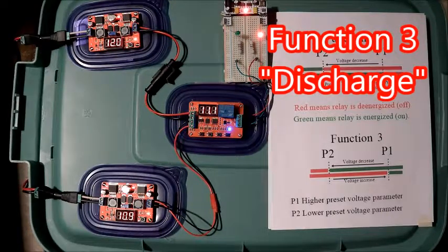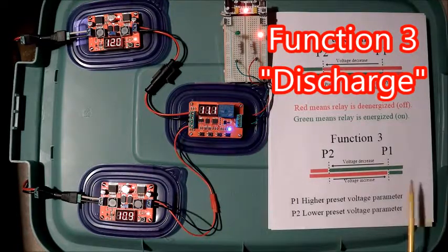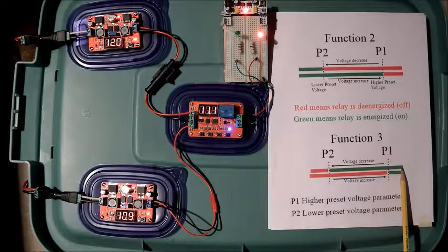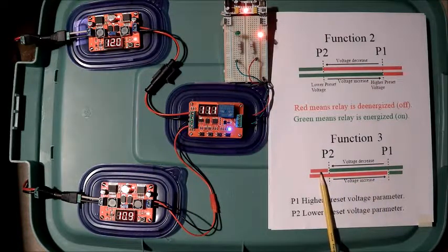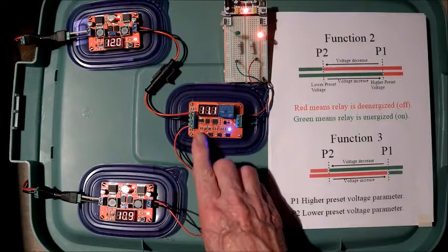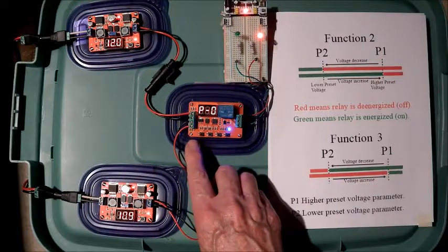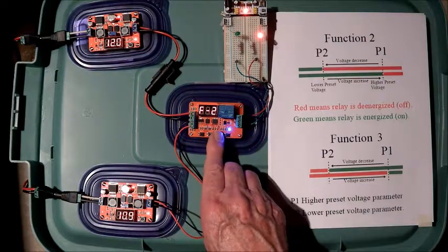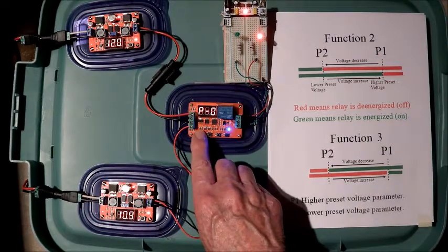Going to Function 3. Function 3 is the mirror of Function 2 in that the decreasing voltage we have the relay energized or on. When it reaches the lower value, it will turn off the relay. It'll stay off until it reaches the higher value. Going in and setting up for Function 3. At P0, I hit the Set button. I'm at Function 2. I will increase that to Function 3. Save it. Go back to Operational Mode.